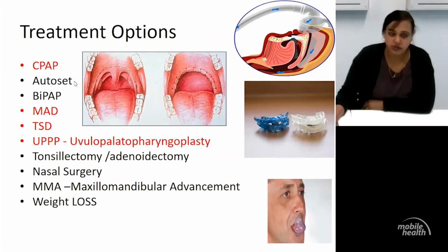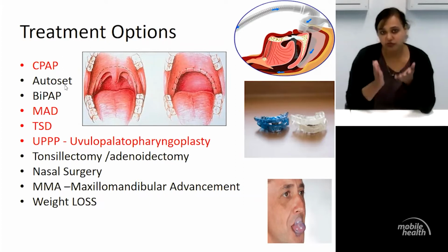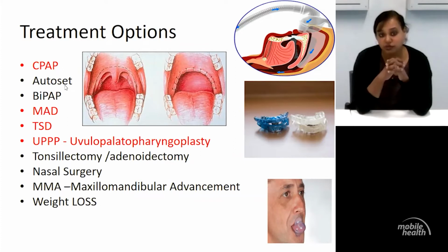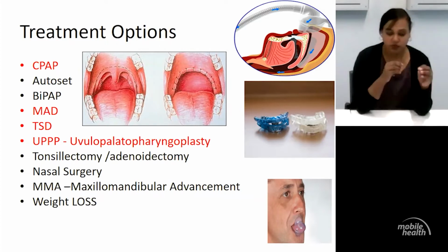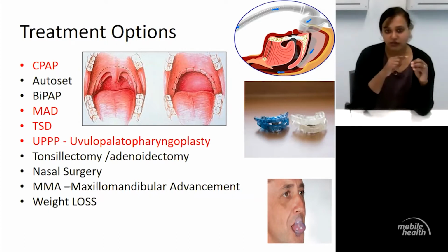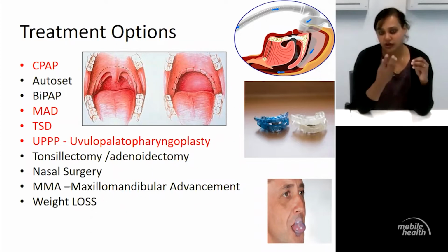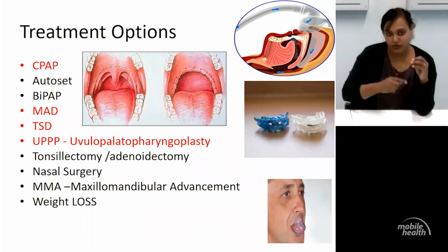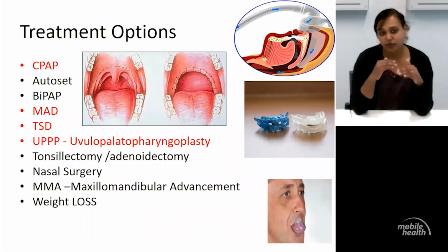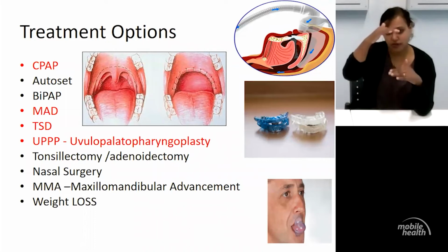With the AutoSet machine, it's similar to a CPAP, however, it's variable pressures. So there's two different set pressures on this machine. Some people find it more comfortable to use the AutoSet because it starts off at a very low pressure, and in the night, it senses how the breathing is for the patient, and it'll self-adjust up and down depending on the patient's breathing. So it's got a minimum pressure setting, and it's got a maximum pressure setting.